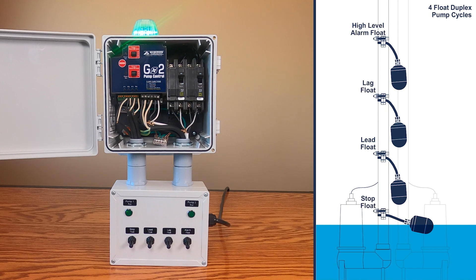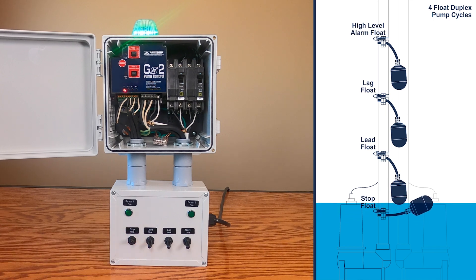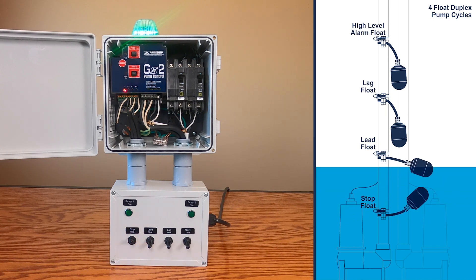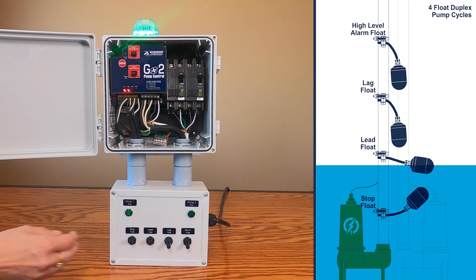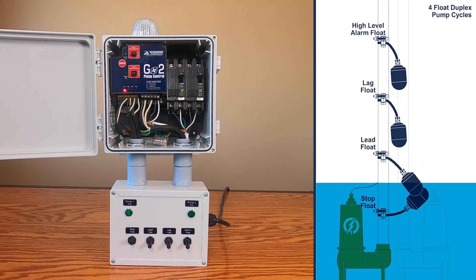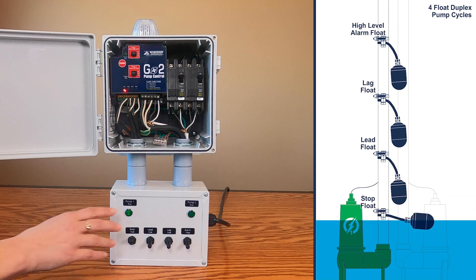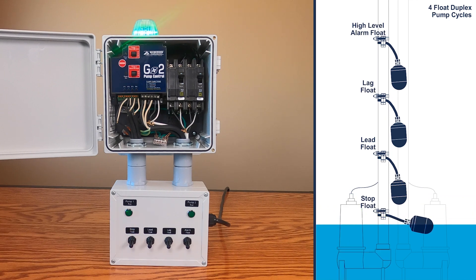On the second pump cycle, as the water rises, the off float will activate. The water level continues to rise and the lead float will activate and pump 1 will turn on. As the pump is lowering the water level, the lead float will tilt down, but the pump will remain on all the way down to the off float. This completes the second pump cycle. The pump alternates after each pump cycle.